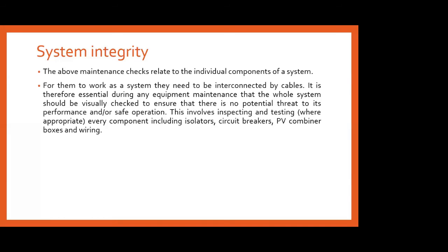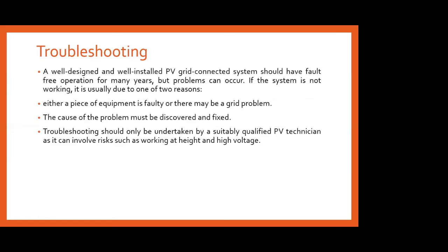Okay, and whether safe operation is taking place, and this involves, what are the things it is involving? It is involving inspecting and testing every component, including your isolators, circuit breakers, the combiner boxes, the inverters, and the DC and the AC wirings. Each and everything has to be checked, and of course once it is checked, how to troubleshoot or how to come up with a solution for your complete PV system. Okay, and those things we are calling troubleshooting.